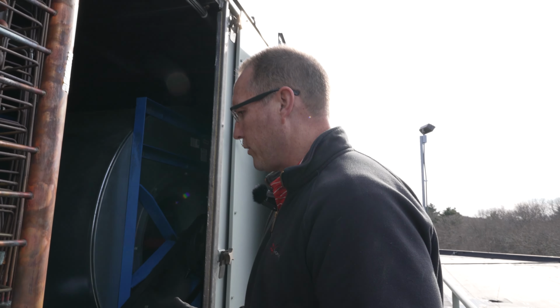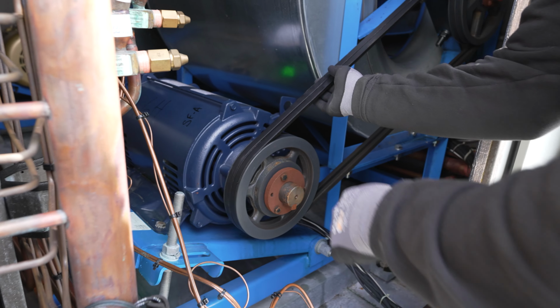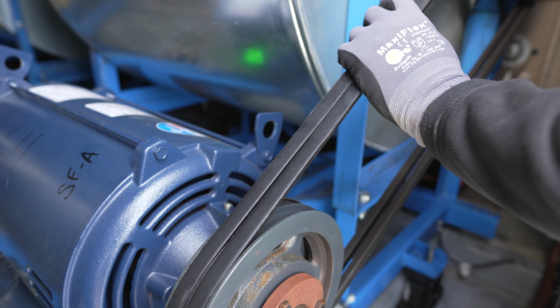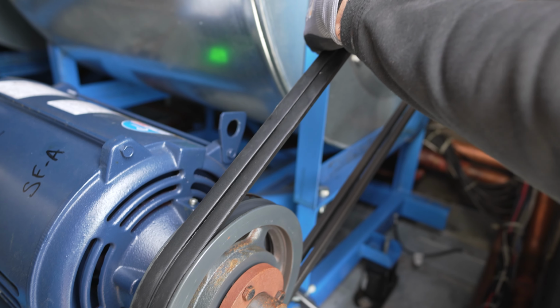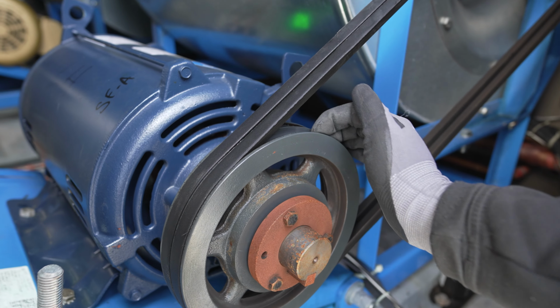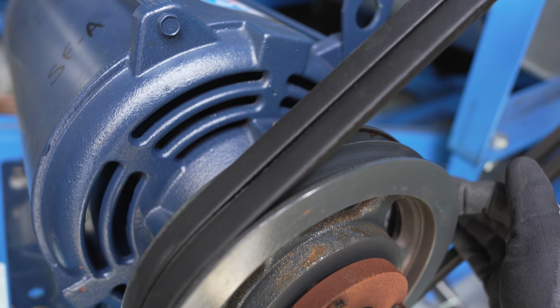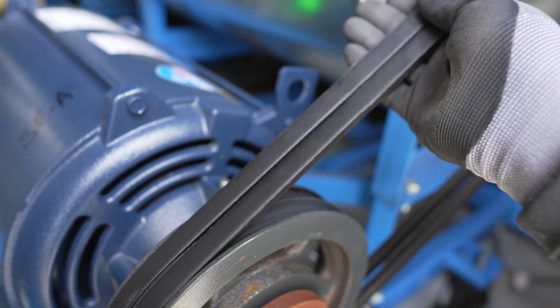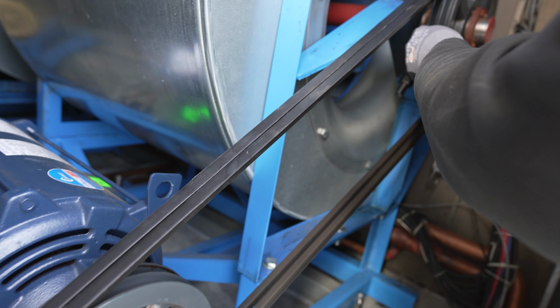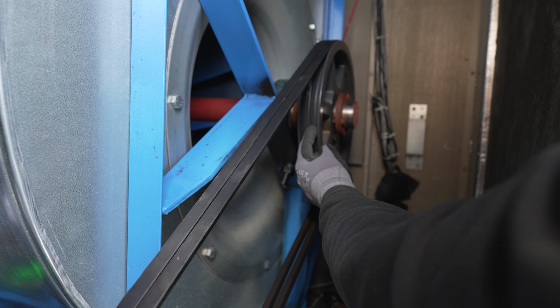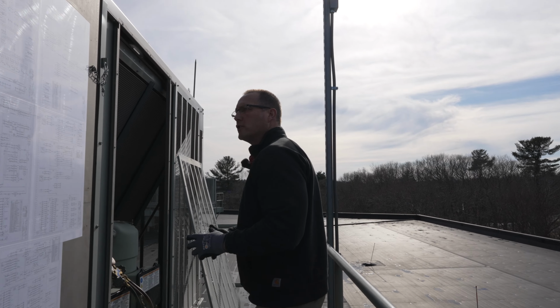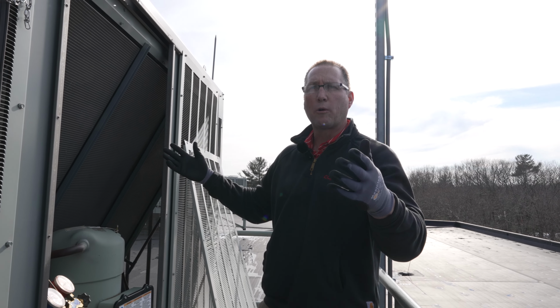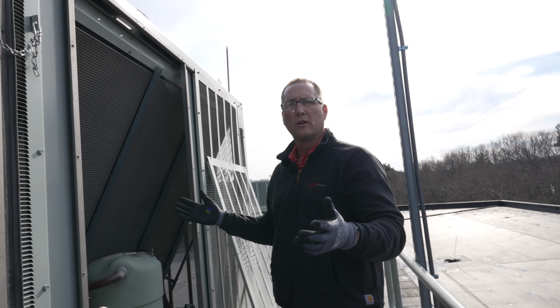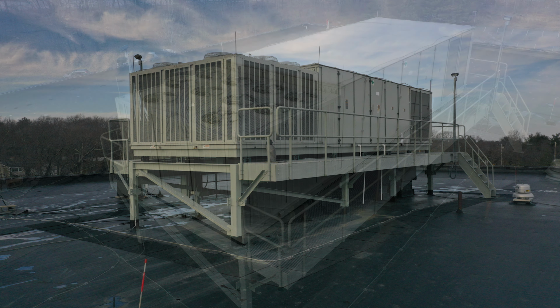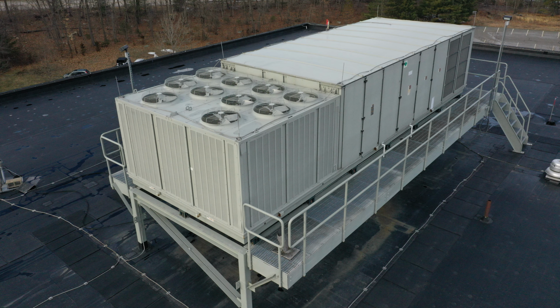Coming back into this unit that we've already been at, I wanted to show you the importance of the belts. We have to make sure these belts are clean, with no cracking throughout. The other thing is the sheave here. We want to make sure it's clean and there's no rounding that's going to deteriorate these belts and shorten their life. Same with the pulley up here. They'll spin this through and check to make sure there's no grooving going on. I just wanted to finish up by saying that the unit we're talking about today is considered a package rooftop unit. Really everything, the condenser and the evaporator, meaning the cooling coil, is all tied into one unit.